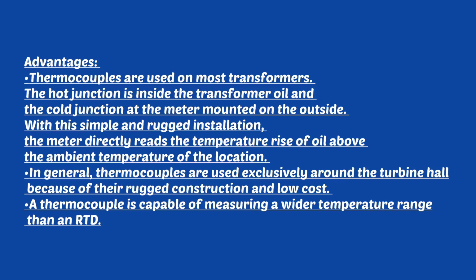Here are the advantages and disadvantages of thermocouple. Advantage 1. Thermocouples are used on the main transformers. The hot junction is inside the transformer oil and the cold junction at the meter mounted on the outside. With this simple and rugged installation, the meter directly reads the temperature rise of oil above the ambient temperature of the location. 2. In general, thermocouples are used exclusively around the turbine hall because of their rugged construction and low cost. And 3. A thermocouple is capable of measuring a wider temperature range than an RTD.